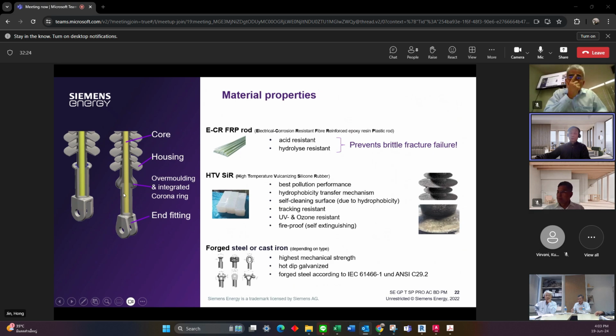For long rod insulators for transmission lines, the most critical point is the joint, because here is the crimping point between the core material and end fitting. This is also the most critical point for moisture ingress, partial discharge, and electrical corrosion. Those points are very critical and must be protected very carefully. So we have an over molding design. After crimping of the core material and the end fitting, we use over molding silicone rubber to completely cover the joint point to avoid moisture ingression. This is our special design.